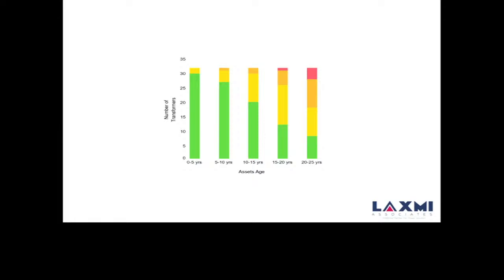The more you migrate from 5 to 10 years or 10 to 15 years, this green zone is going to reduce—it will be taken over by the yellow zone, meaning you have average health. Then it moves to monitoring, and red goes to alert. This is the whole journey of the transformer in terms of health index.